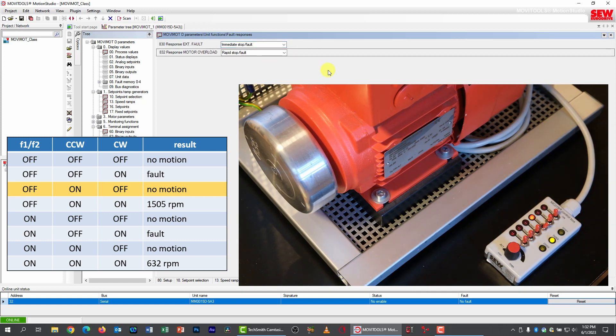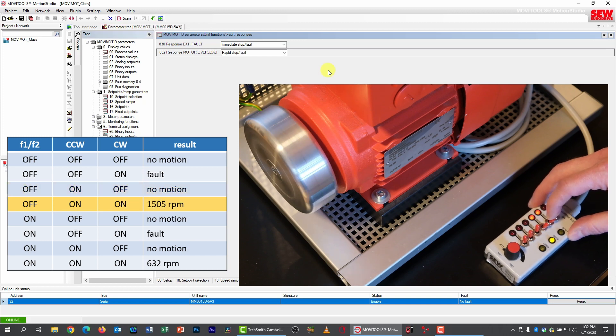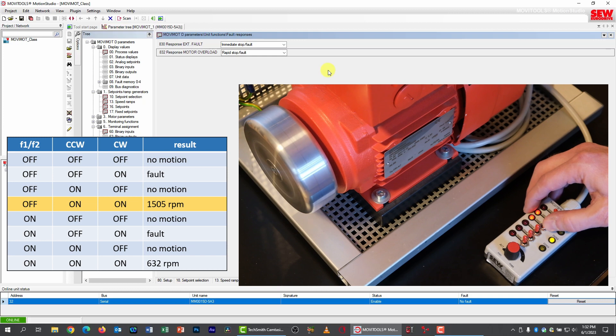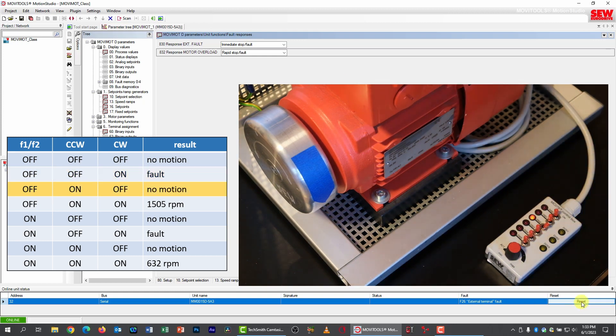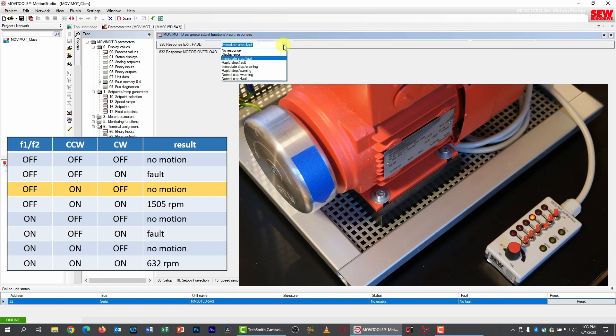That's something important to be aware of: when you clear a fault, the Movimot will try to go back to doing what it was doing at the time of the fault, which could include running — and that could be dangerous. Before clearing a fault, always ask yourself if anything bad could happen, and if so, maybe disable the drive first. The drive is running; let me confirm the second speed works, then I'll trip the external fault sensor. The drive ramps to a stop fairly slowly — using the normal stop ramp by default, which is not very fast.